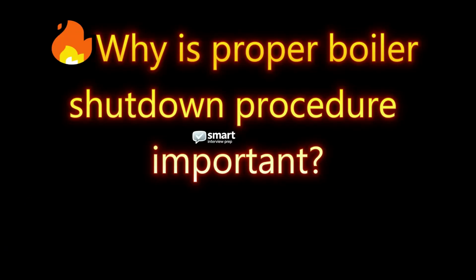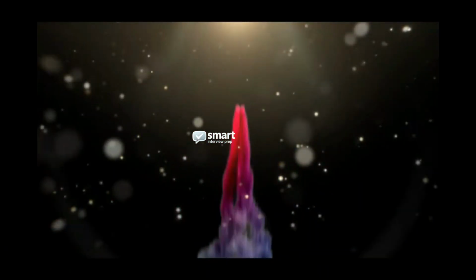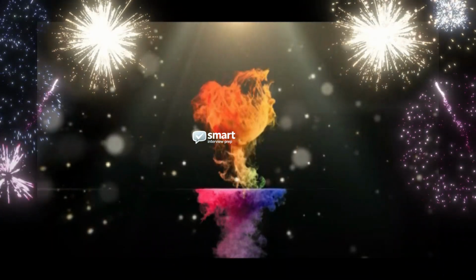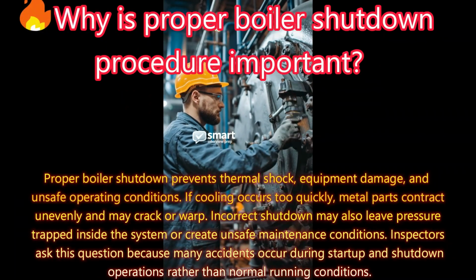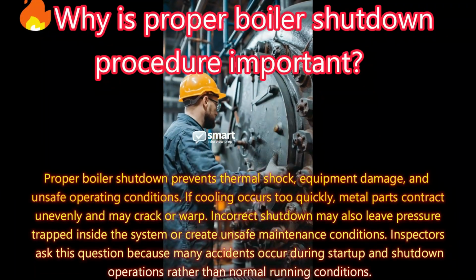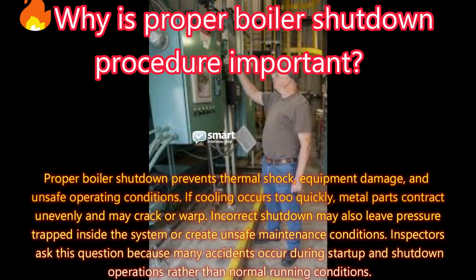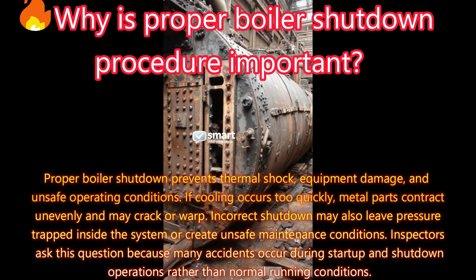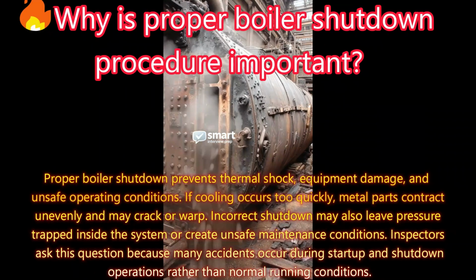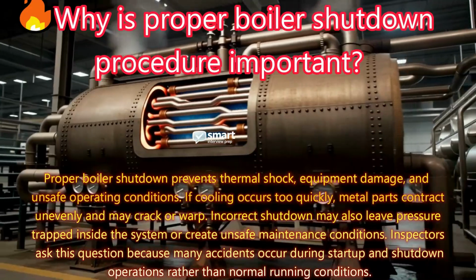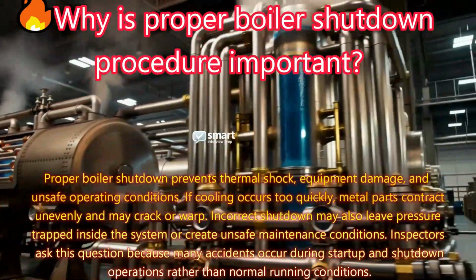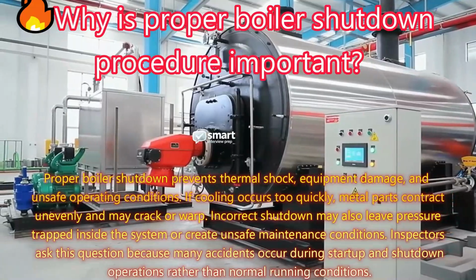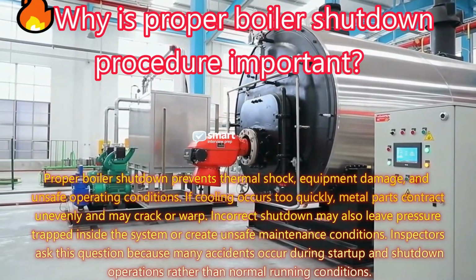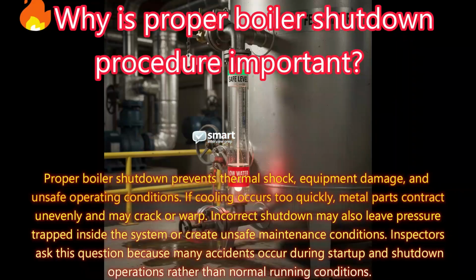Why is proper boiler shutdown procedure important? Answer. Proper boiler shutdown prevents thermal shock, equipment damage, and unsafe operating conditions. If cooling occurs too quickly, metal parts contract unevenly and may crack or warp. Incorrect shutdown may also leave pressure trapped inside the system or create unsafe maintenance conditions. Inspectors ask this question because many accidents occur during startup and shutdown operations rather than normal running conditions.